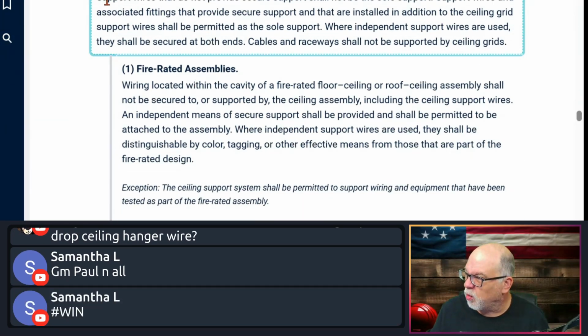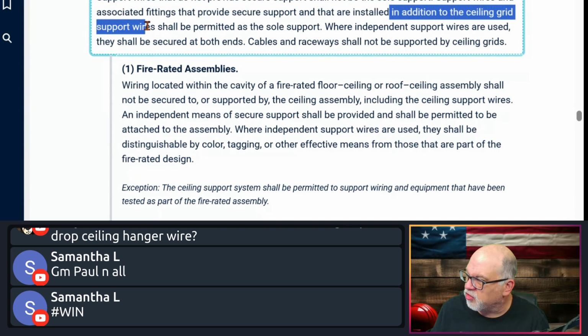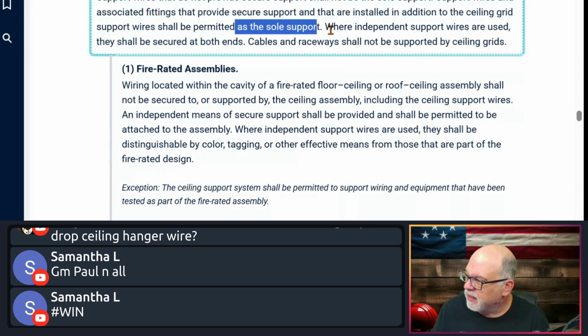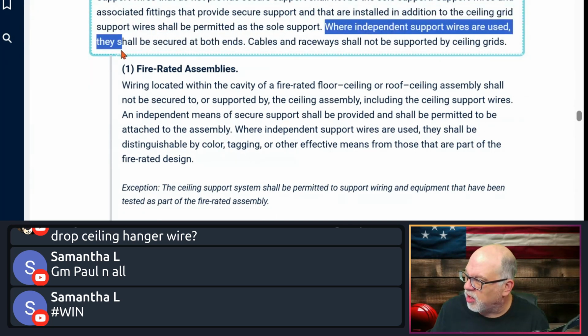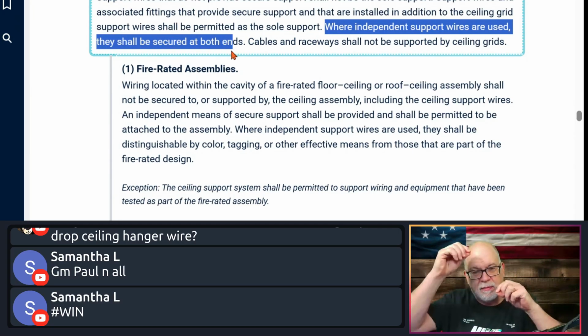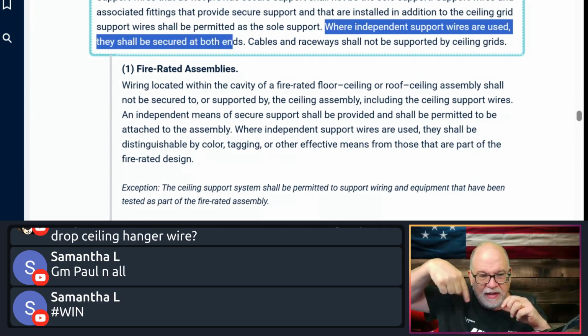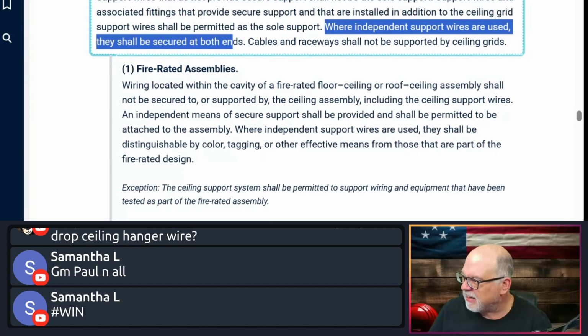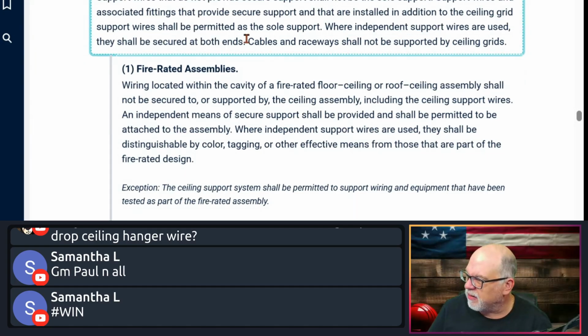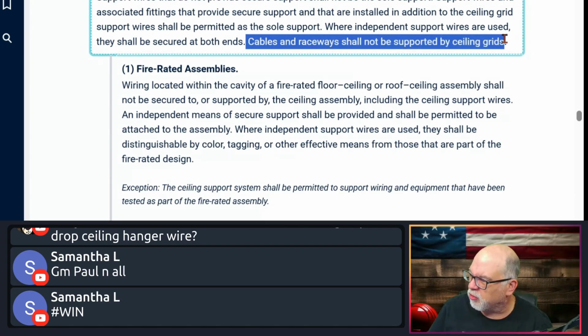So here it says support wires that do not provide secure support shall not be used as a sole support. Support wires and associated fittings that provide secure support and that are installed in addition to the ceiling grid support wires shall be permitted as the sole support. If independent support wires are used, they shall be secured at both ends. That means you connect them at both ends, not one of those trapeze type things that I see people do. It has to be secured at both ends. Here it says the cables and raceways shall not be supported by the ceiling grid itself.